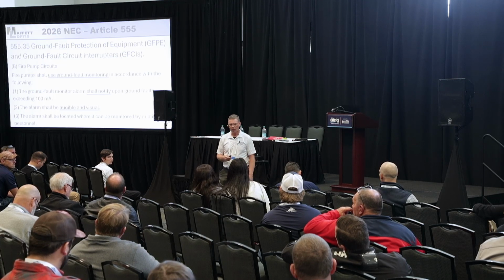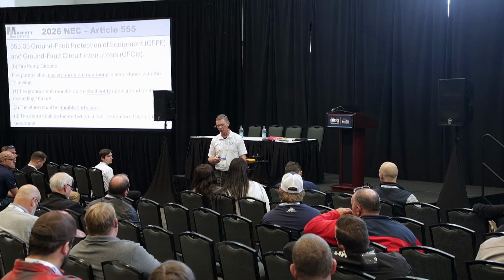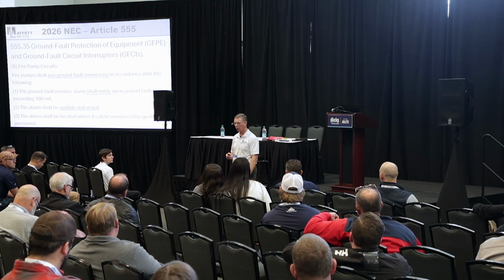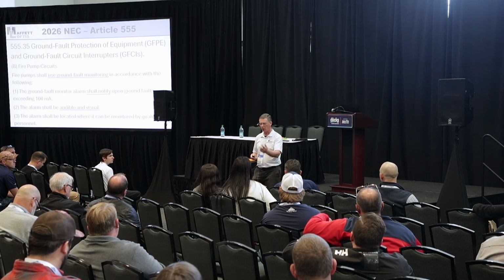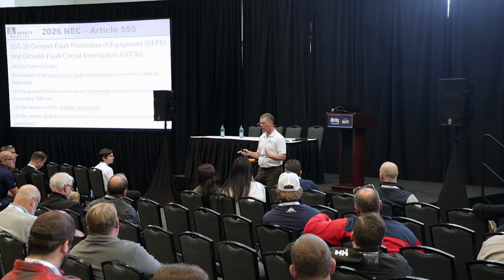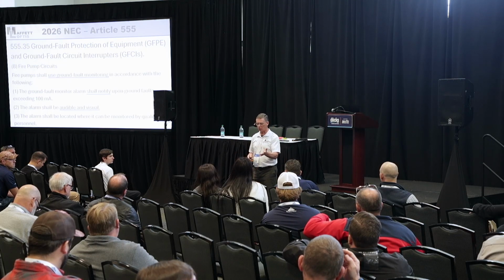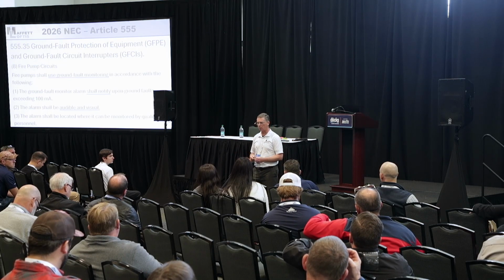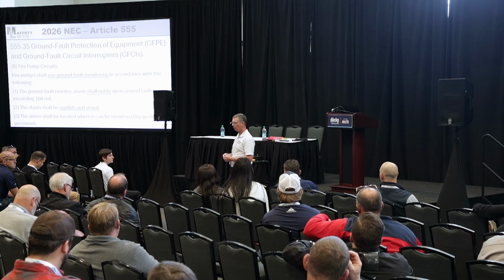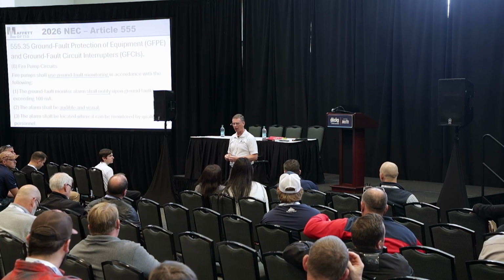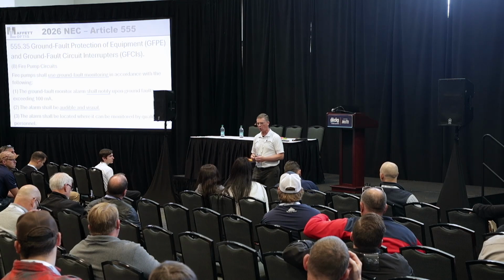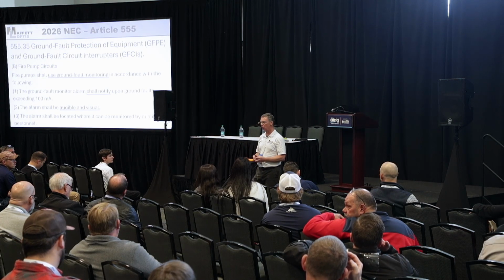What's that? It's a dry hydrant. Yes, it's not an energized hydrant, and they're only energized when somebody turns that fire pump on. So the question was about these systems that we're designing. We have designed wet systems because the jurisdiction required wet systems, but most of these types of fire pumps will be a dry type system with dry standpipes, only energized when the fire pump gets turned on.